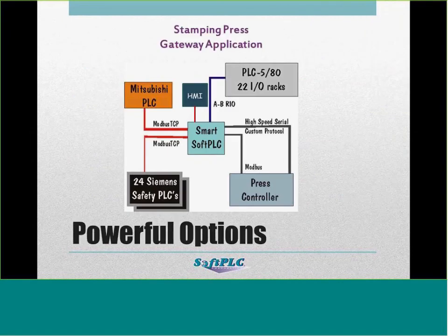So just go back to this application here. We actually could have replaced that PLC5 with the Smart SoftPLC and driven all those 22 I/O racks directly and eliminated the need for all that multiplexing and rigmarole that was going on, but the customer at the time wasn't ready to do that.